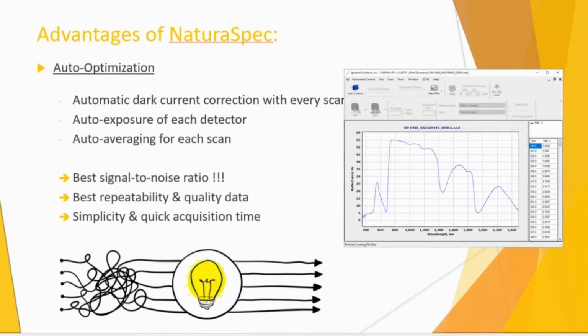Each detector, being in a different spectral range, will react differently to the light signal. And in one particular range, you may need more exposure to the detector, so a longer time for the detector to be illuminated than in another range. Our software is clever enough to decide what is the best optimum exposure time for each detector independently. So by doing that, you're going to make sure that not only you have the best signal-to-noise ratio for each detector, but you have the best signal-to-noise ratio overall for your complete spectral data.